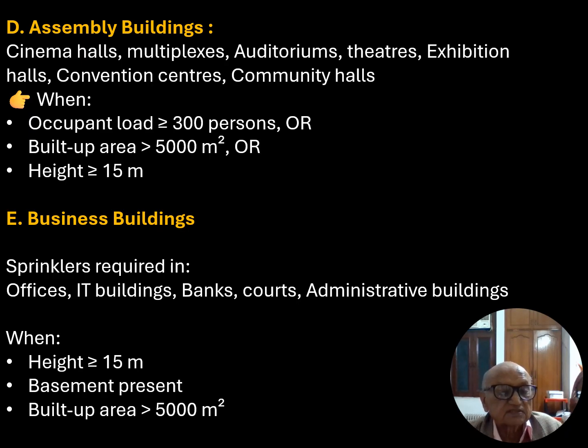In the case of business buildings, sprinklers are mandatory to be provided in offices, IT buildings, banks, courts, and administrative buildings, if the business building is more than 15 meters in height, a basement is there, and the built area is more than 5,000 square meters.